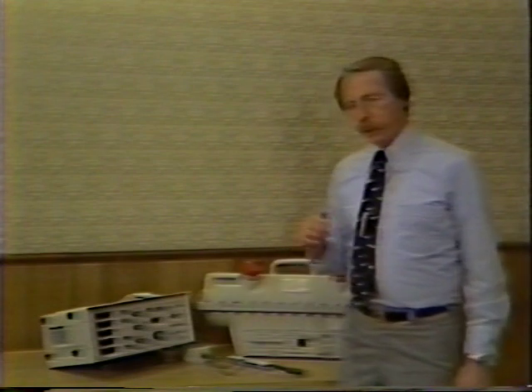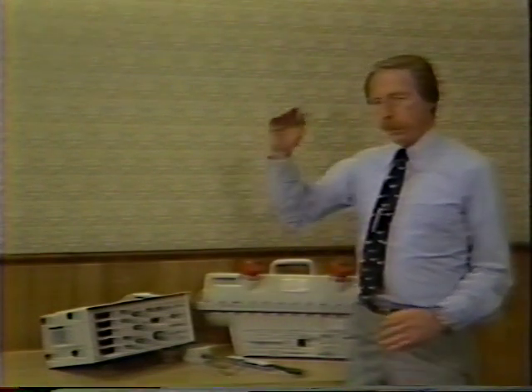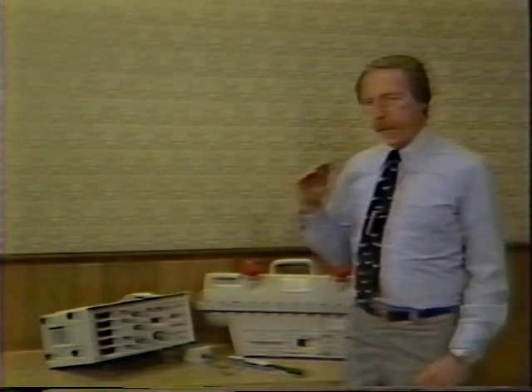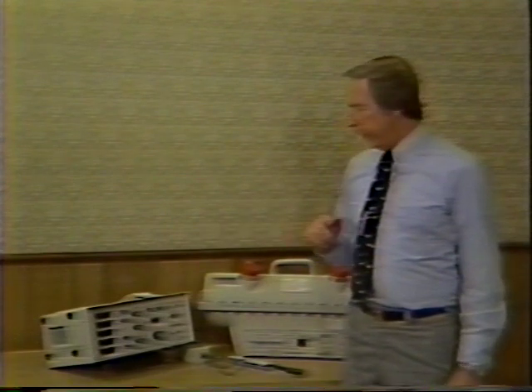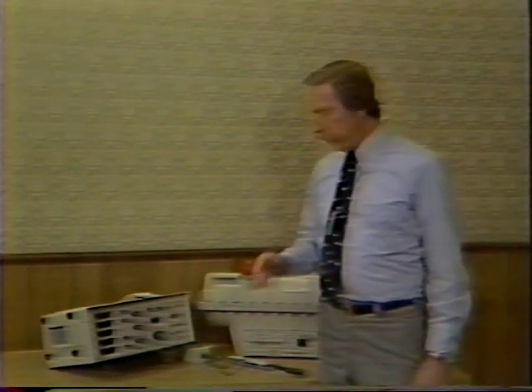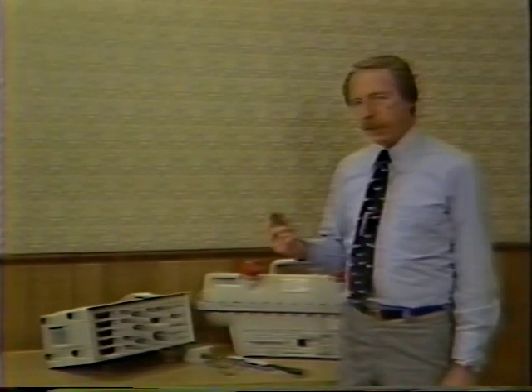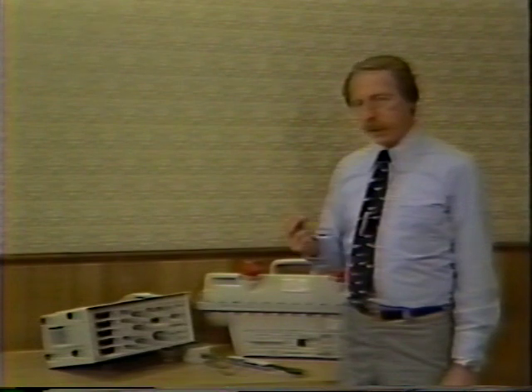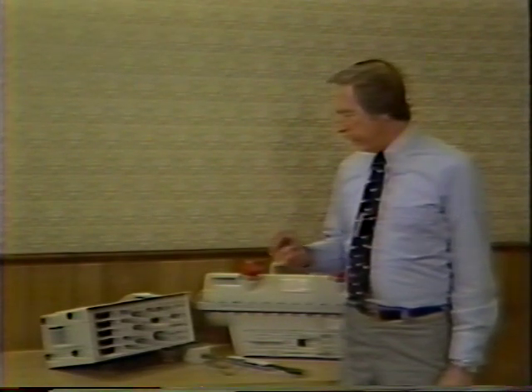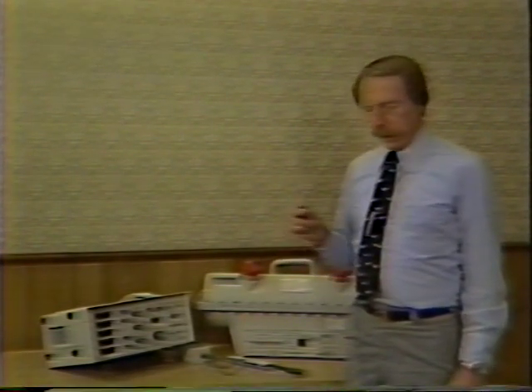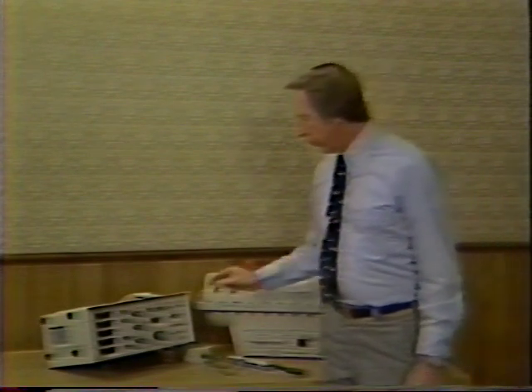One cautionary note: in a percent mode, when we move the voltage back down, we cannot trigger the unit. It is necessary, as you come back down in voltage, to push the reset, clear the memory, and take two more shots. One to sense the kV in the generator, and the second to set the reference level. This is a common problem in usage of this equipment in the field.